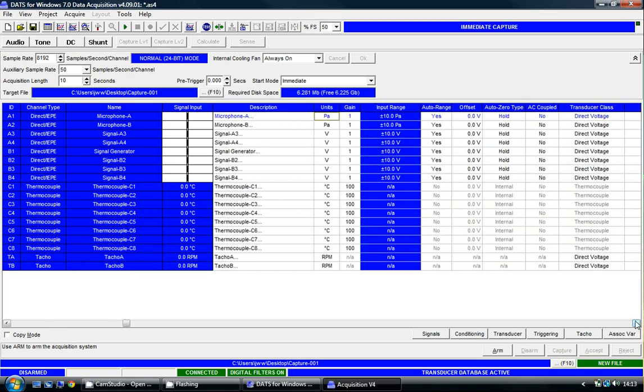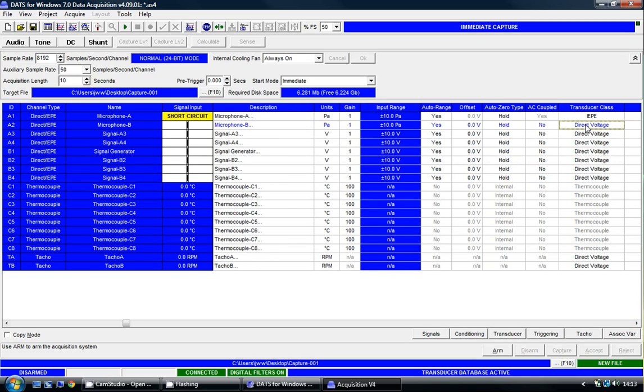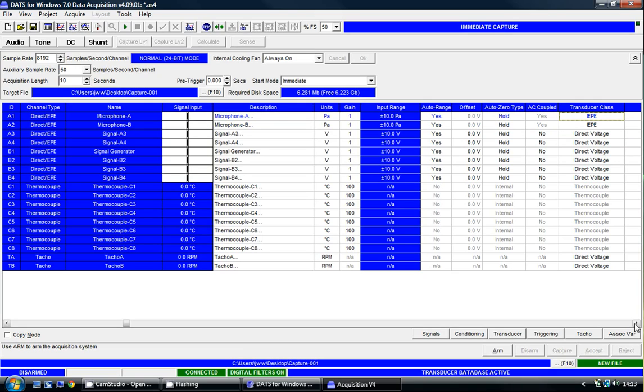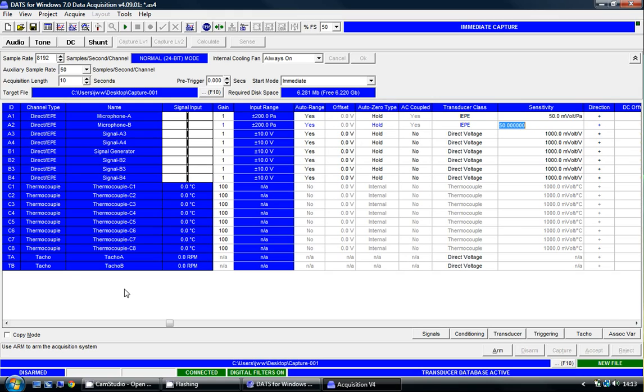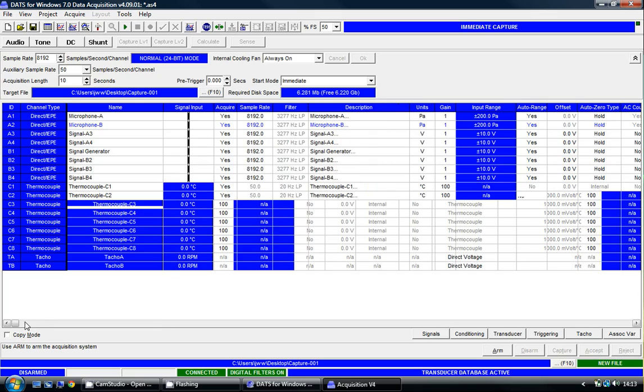I'm going to set the transducer class to IEPE for both of those sensors, as they're both IEPE microphones. Both these microphones have a sensitivity of 50 millivolts per Pascal, so I'm going to set those sensitivities as well.